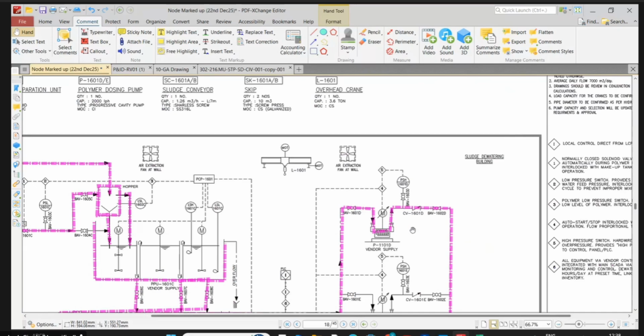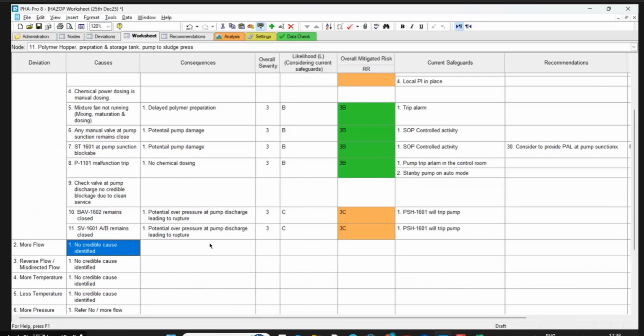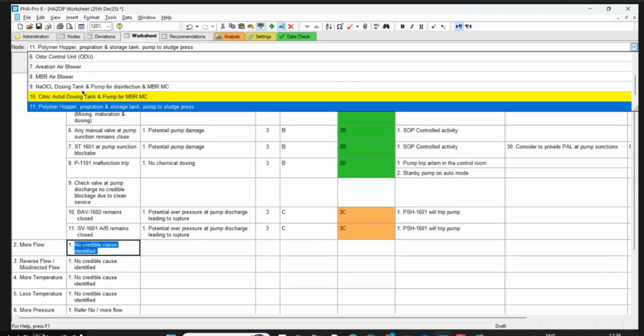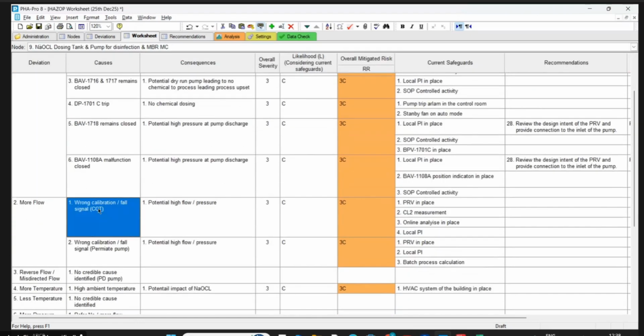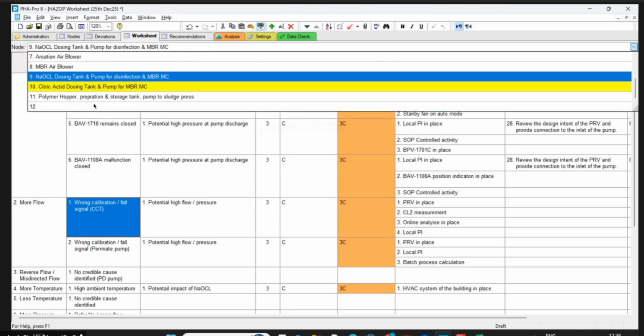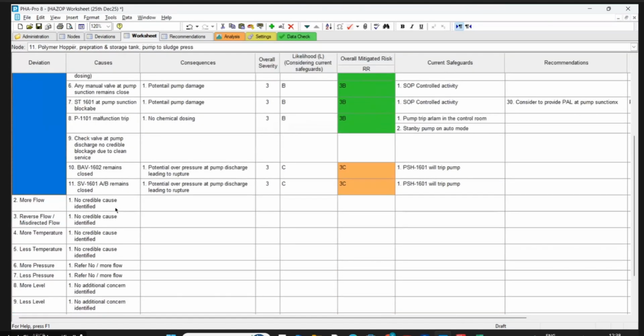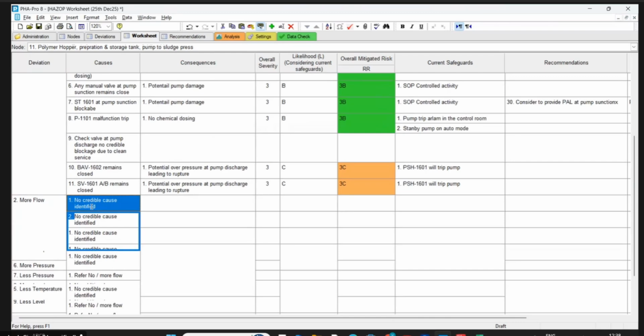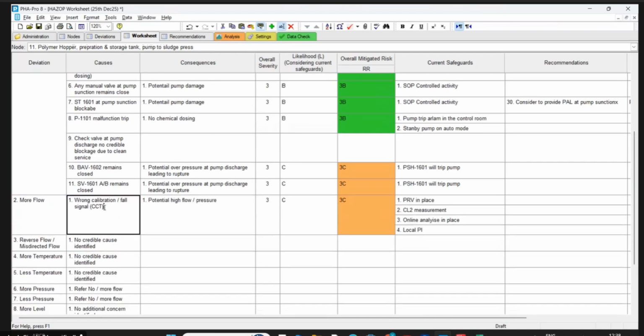No, it is everything VFD. It should be interlocked. VFD, interlocked with the feed pump of the screw. Yes, so I have to take it. Screw interlock. Yes, interlocked with the screw. These are interlocked with the feed pump of the screw press and the screw. Once it is working, the pump and screw should come on together, always.